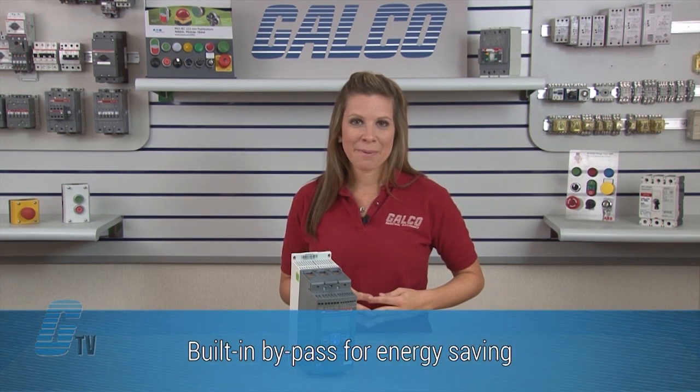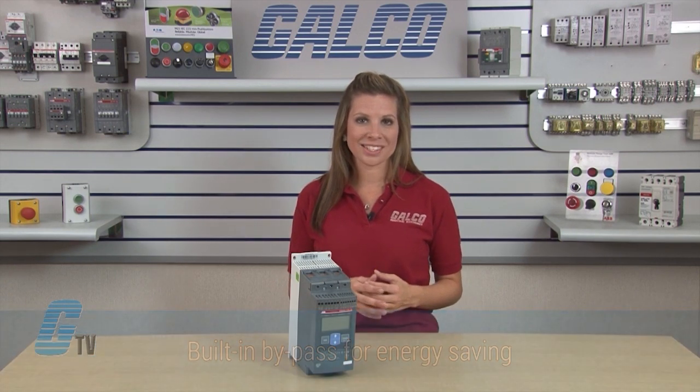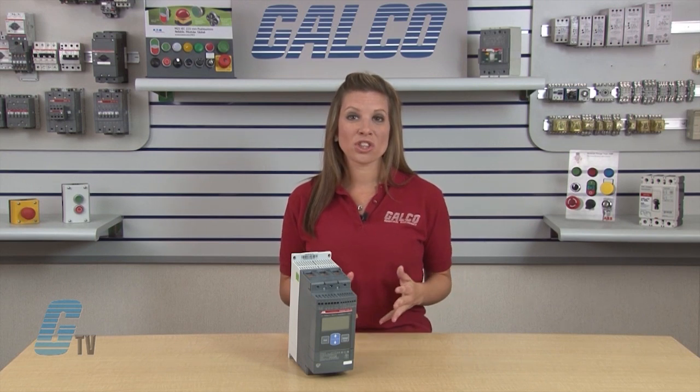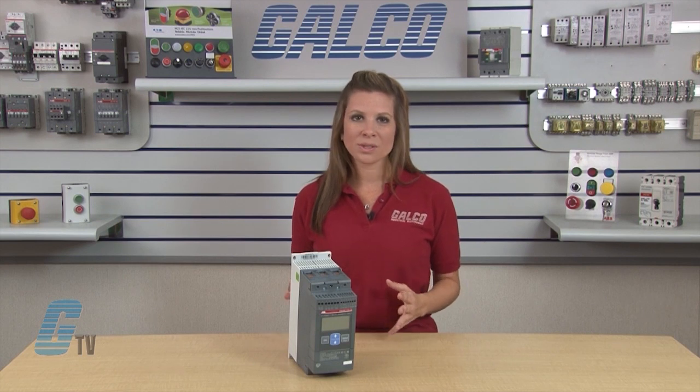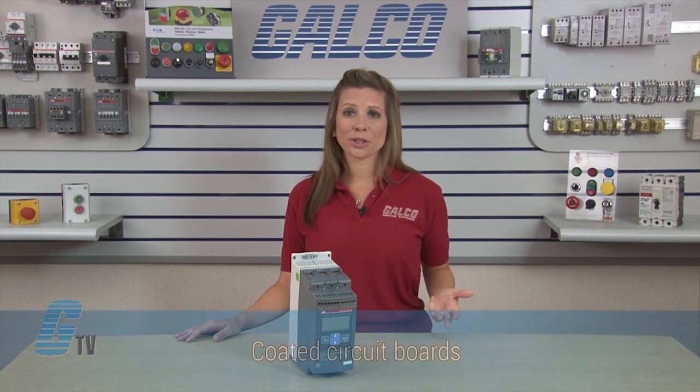Using the built-in bypass after reaching full voltage will greatly reduce power loss and thereby save energy. In the PSE Soft Starter range, the bypass is built in on all sizes, which gives the most compact starting solution and reduces the need for wiring during installation.